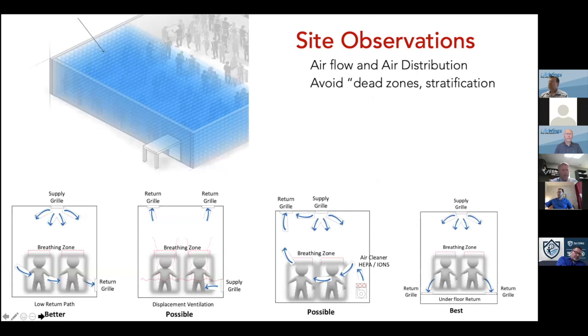So just to recap, I didn't add a lot of photos, but we have a lot of existing photos of classrooms with ceiling supply grills and ceiling return grills. Obviously, that's not the best choice. We see a lot of short cycling when you get to a distribution system like that. So this is a good graph, and the lower 4 examples are ways that we can improve that. One is supplying high, pulling that air across to a low return grill, or supplying low and going the other way, with return grills at the top. Either one of those actually pulls that air across the breathing zone and back up without mixing.